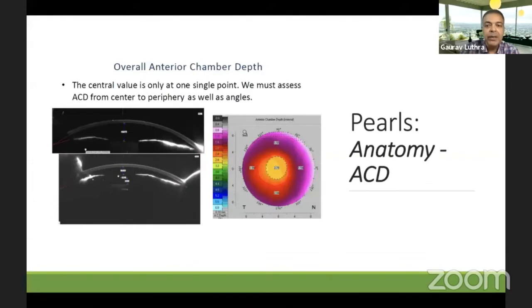And once you are looking at the anterior chamber depth, let's just not look at the number which comes out of the A scan. It would be good if you have 2 devices to do it, preferably an optical biometer would be ideal.